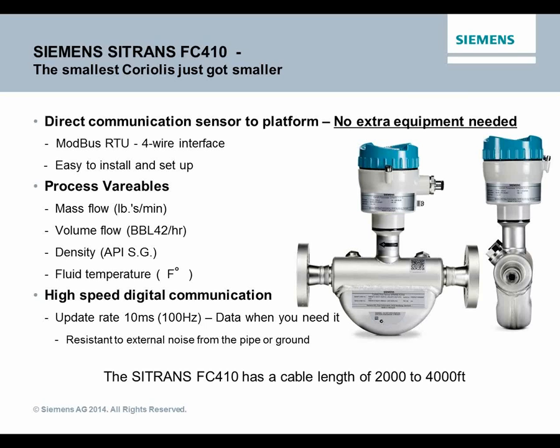As I said, this is one of the newer ones. Other devices that we sell still do the 4 to 20, still do DeviceNet, and HART, of course, is still available. It's just that this is one of the newer ones that we thought we would highlight. So the process variables in this one, of course, mass flow, volume flow, density, and fluid temperature are still standard and available. The update rate, the data is pulled off the meter 100 times a second, at 100 hertz. So every 10 milliseconds, you get data when you need it.